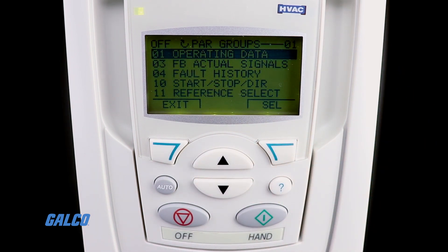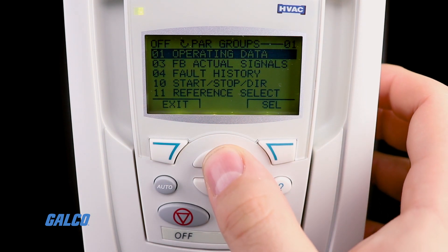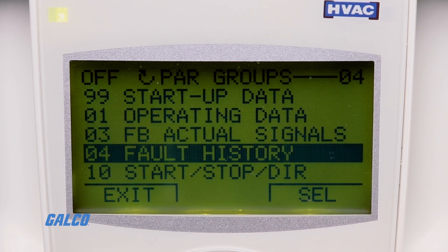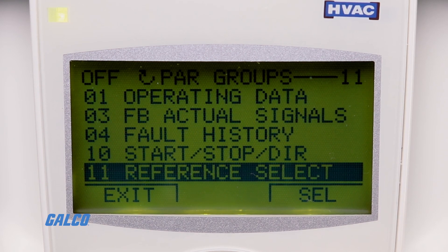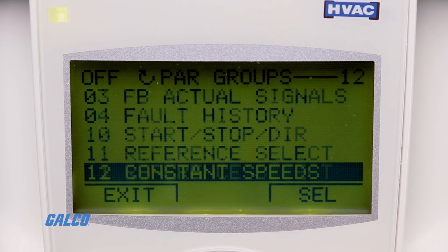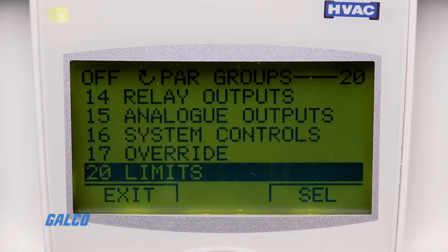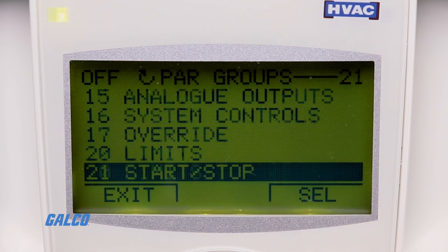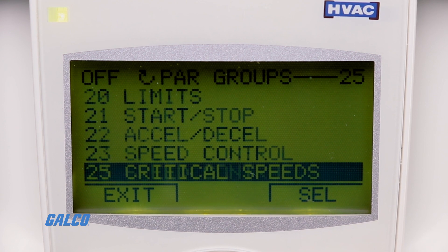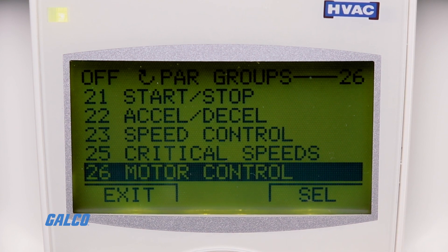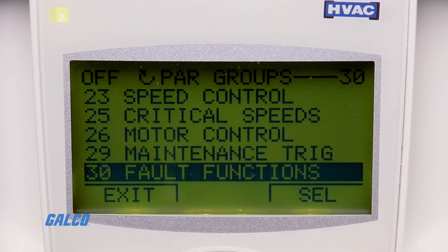The most common parameter groups that you may need to adjust in order to prepare for a basic startup configuration are 99 startup data, 10 start stop direction, 11 reference select, 20 limits, 21 start stop, 22 accel decel, 26 motor control, and 30 fault functions.